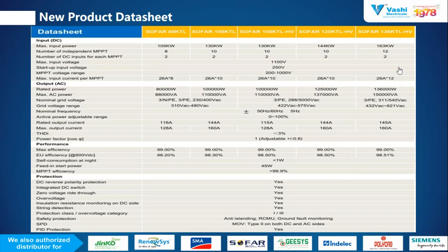Now in the high voltage system, we have a range of 100 kilowatt, 125 kilowatt and 136 kilowatt. This high voltage system, we're working with the three-phase 4-wire system only. So this has two main focus features. It is working with the three-phase 4-wire system. This range of inverters is provided with the type 2 SPD at AC and DC side inbuilt. It is very much compatible for commercial and utility project applications. These new products of 80 to 136 kilowatt HV inverters will be available in September or October in the Indian market.